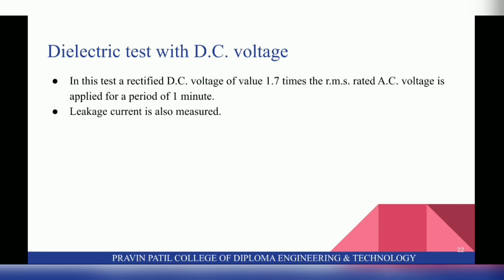Next is the dielectric test with DC voltage. In this test, a rectified DC voltage of value 1.7 times the RMS rated AC voltage is applied for a period of 1 minute. Leakage current is also measured.